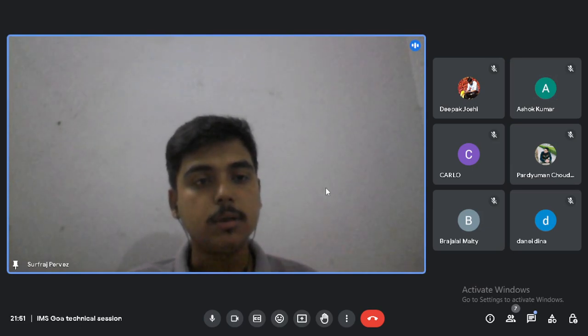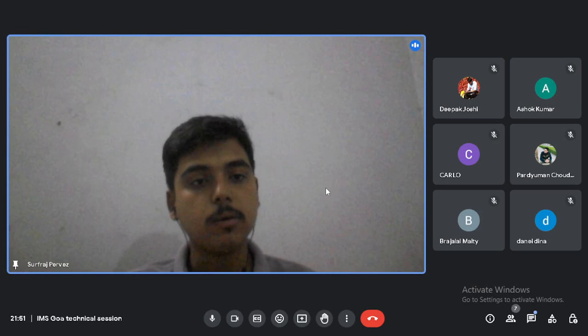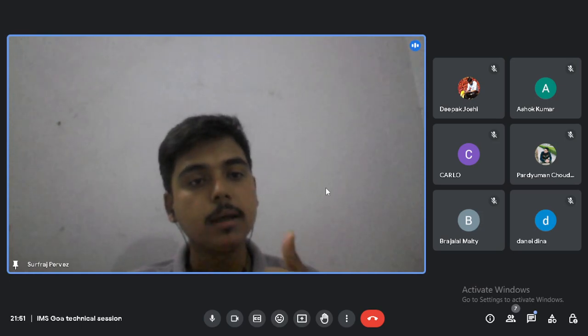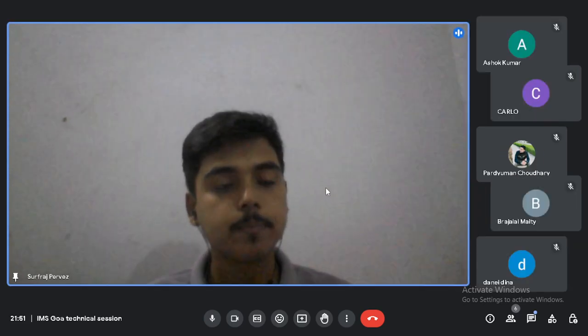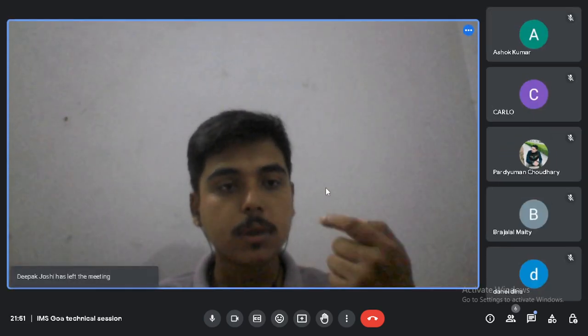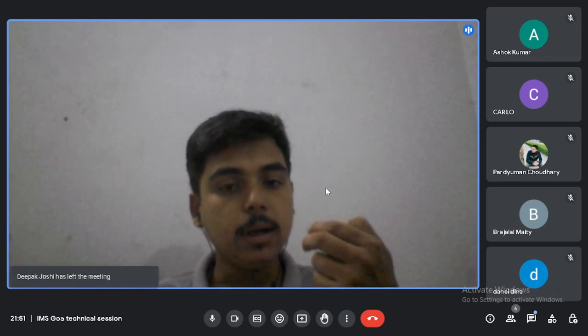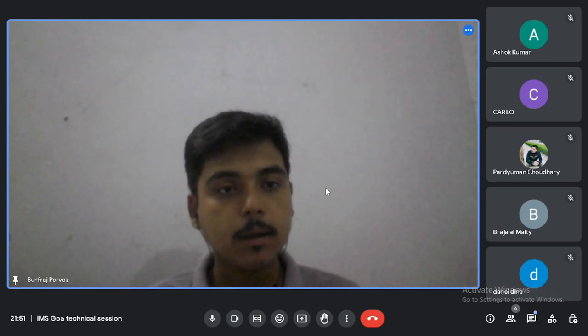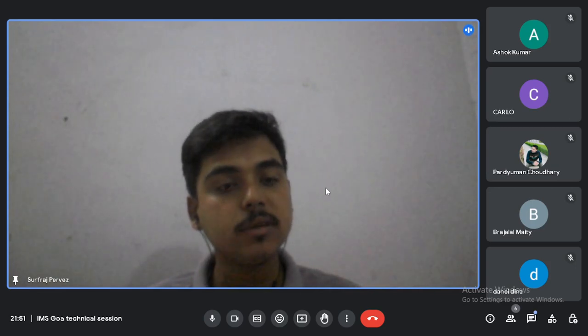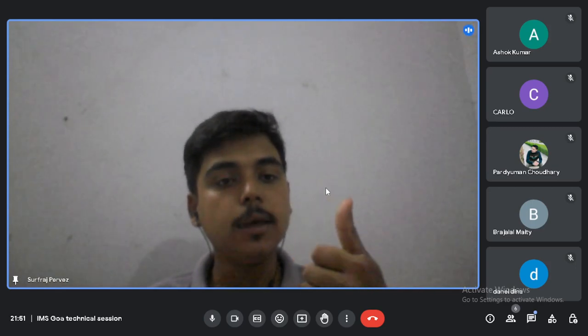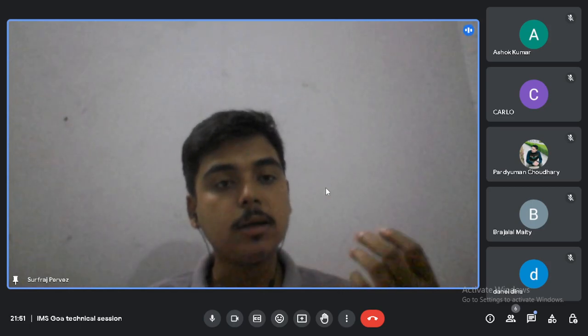All right. So the components of a low water level shutdown are a floater, a trip and a switch. So imagine the gauge glass. It has water, right? And what does a floater do? It floats, right? So this floater is connected to the switch with a trip, and whenever the water level decreases, the floater will come down. If the water level decreases by a certain amount, then this floater will keep hanging, and because of the weight of the floater, the switch will be turned on and it will shut off the boiler.